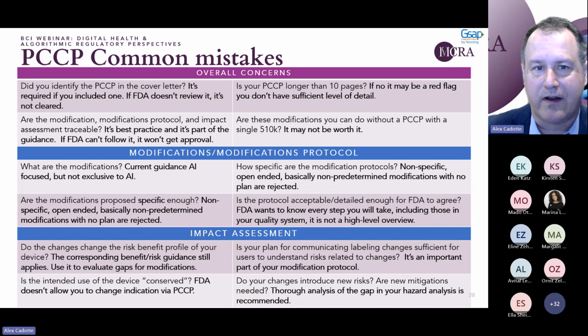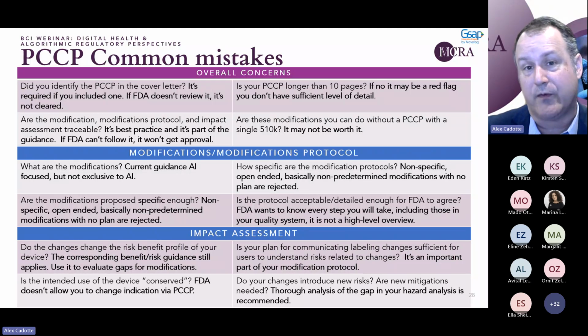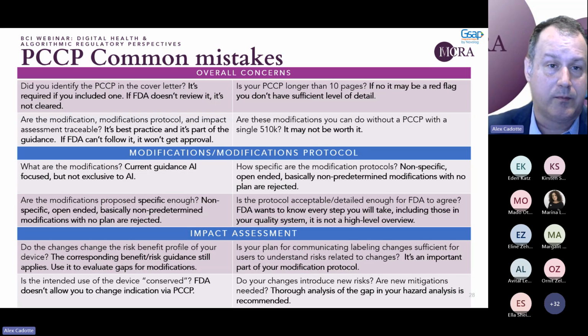Also, before you're ready to submit, is your PCCP roughly 10 pages or less? I'm not saying that that's always the case that it won't work, but generally speaking, that level of detail is usually insufficient, not only for predetermining what your changes are, but also for laying out all the processes and procedures that you would be following in detail for FDA to go over so that they have enough information to approve the PCCP as part of your submission.